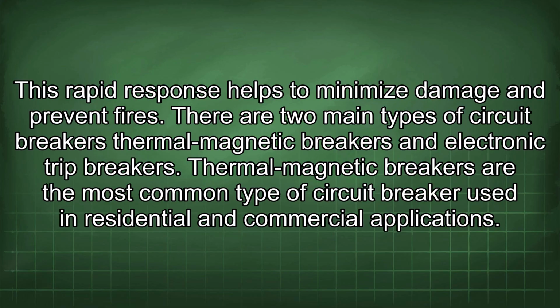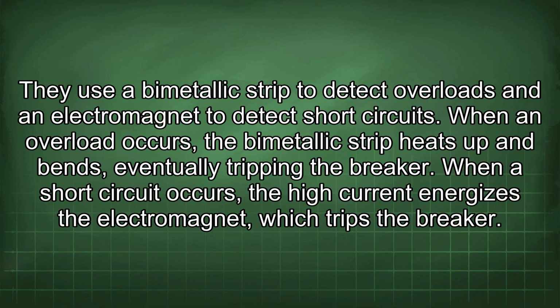There are two main types of circuit breakers: thermal-magnetic breakers and electronic trip breakers. Thermal-magnetic breakers are the most common type of circuit breaker used in residential and commercial applications. They use a bimetallic strip to detect overloads and an electromagnet to detect short circuits. When an overload occurs, the bimetallic strip heats up and bends, eventually tripping the breaker. When a short circuit occurs, the high current energizes the electromagnet, which trips the breaker.